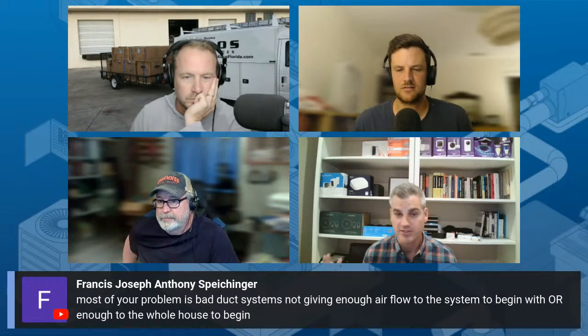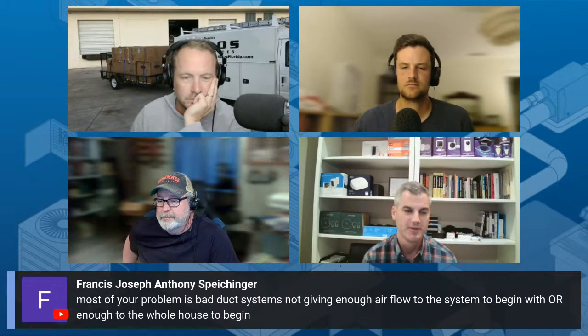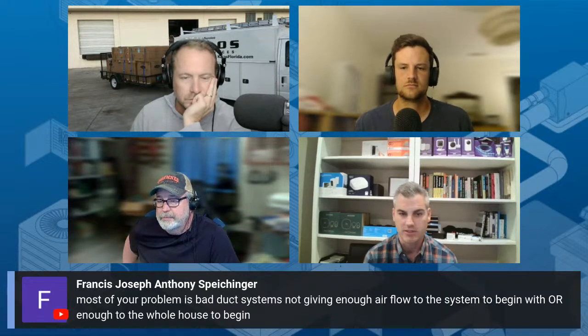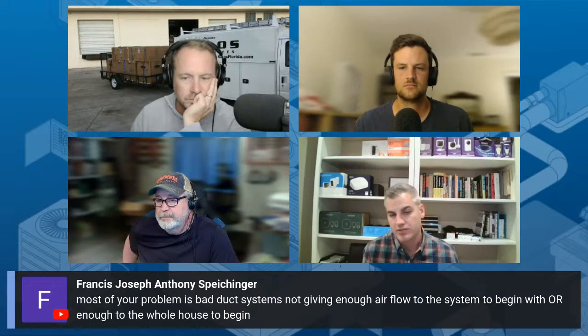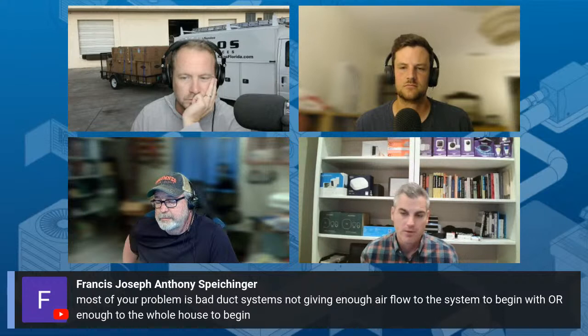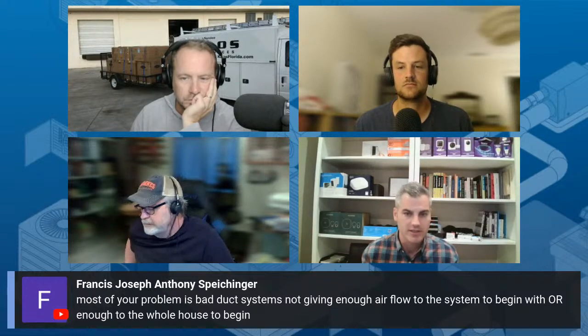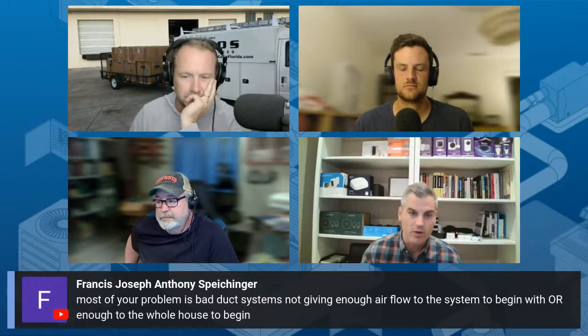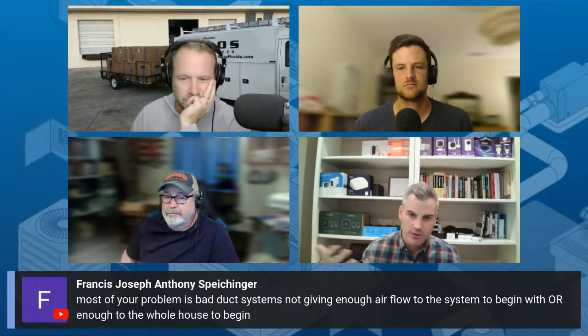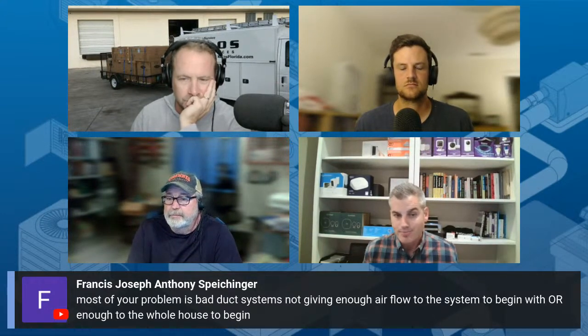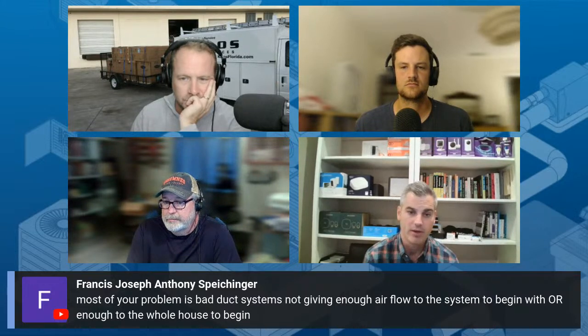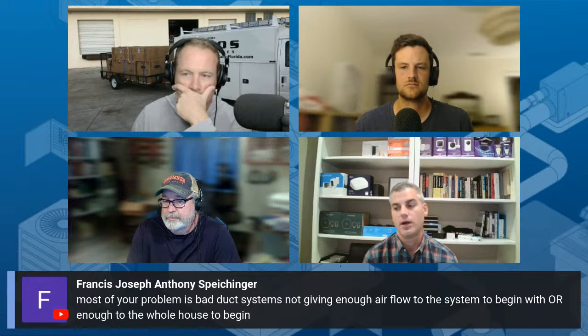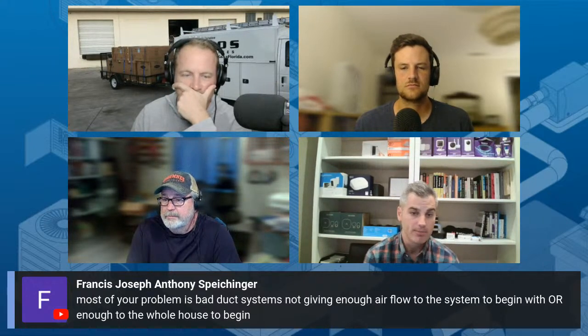There's a bunch of advantages to it, of course, disadvantages too, but we find that to be the most successful way to go. Obviously in a retrofit project, you have ductwork, so a lot of times we're trying to utilize that ductwork. We might set up a TrueFlow and make sure that we have proper airflow, measure the static pressure, just make sure that we're good on that side. But ultimately, we want to make sure that we can move the proper airflow once we've done our Manual J, just make sure we're going to be good there. But yeah, we could just be more targeted with it.